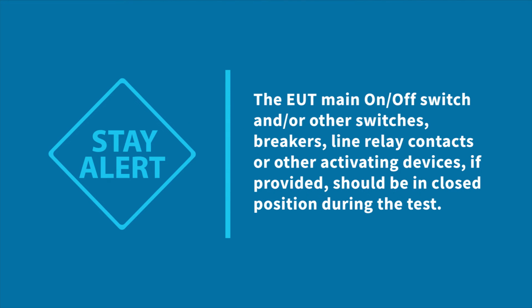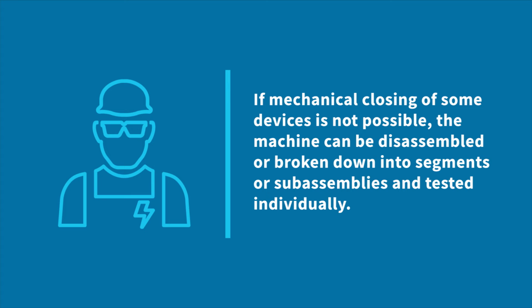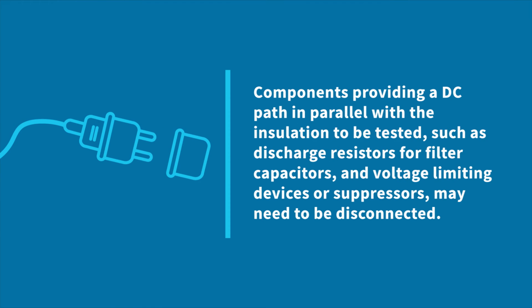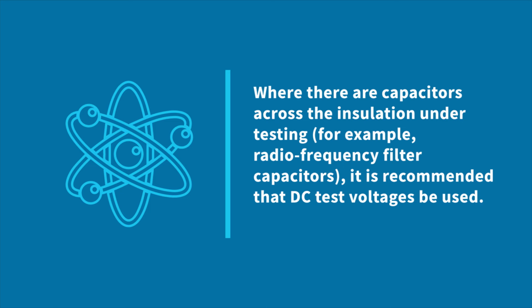The EUT main on-off switch and/or other switches, breakers, line relay contacts, or other activating devices, if provided, should be in closed position during the test. If mechanical closing of some devices is not possible, the machine can be disassembled or broken down into segments or sub-assemblies and tested individually. Components providing a DC path in parallel with the insulation to be tested, such as discharge resistors for filter capacitors and voltage limiting devices or suppressors, may need to be disconnected. Where there are capacitors across the insulation under testing, for example radio frequency filter capacitors, it is recommended that DC test voltages be used.